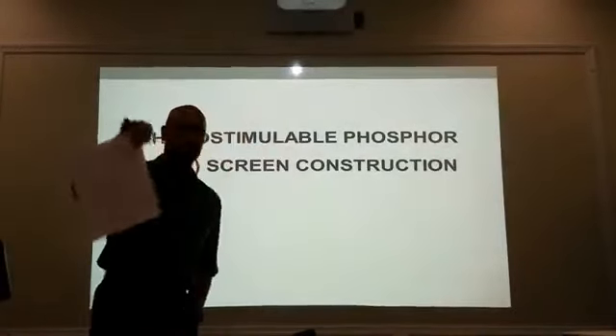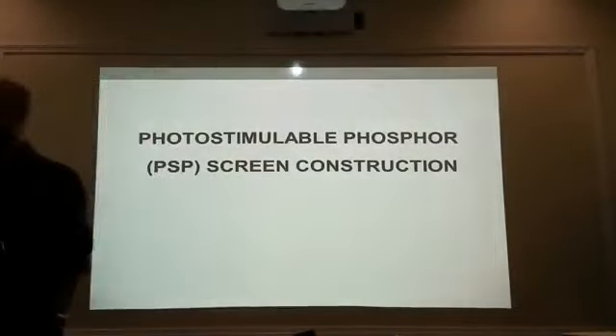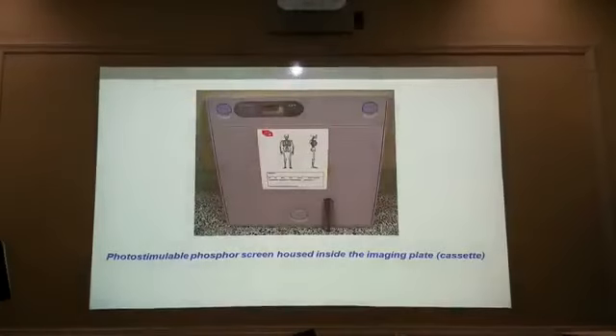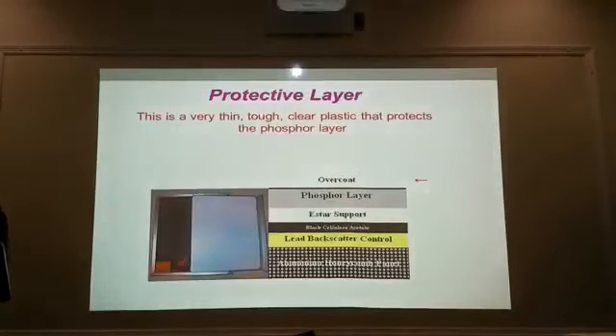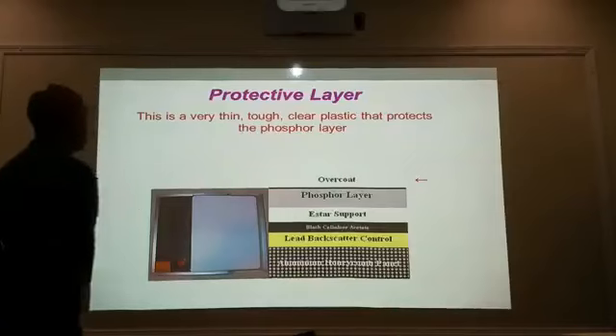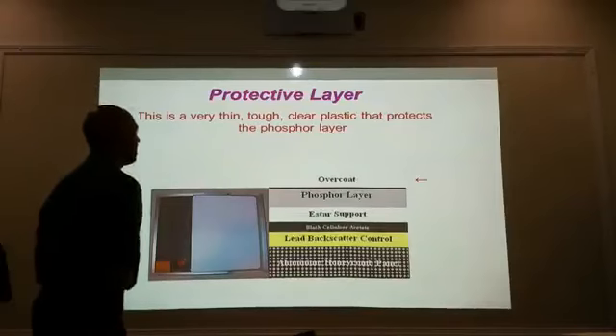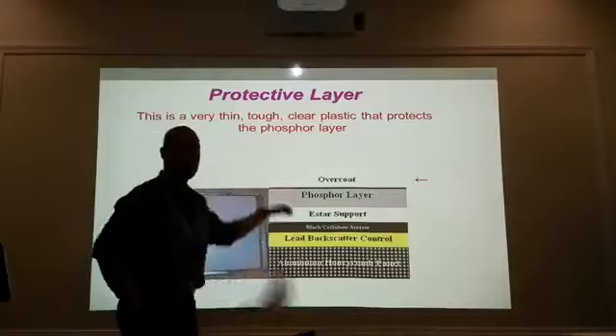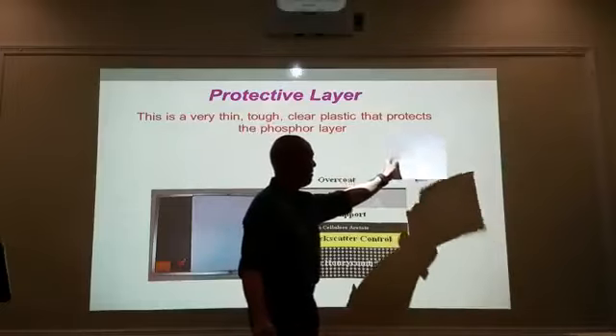Let's talk a little bit about the PSP screen, the photostimulable screen. Like film, it also comes in different layers. The first layer is the protective layer — a very thin, tough, clear plastic that protects the phosphor layer. This is just the very outside of it, and if you notice, there's a kind of a sheen to it, very shiny. The next layer is your active layer, which contains the phosphors.